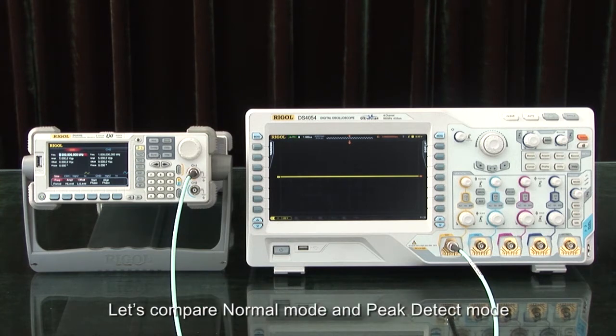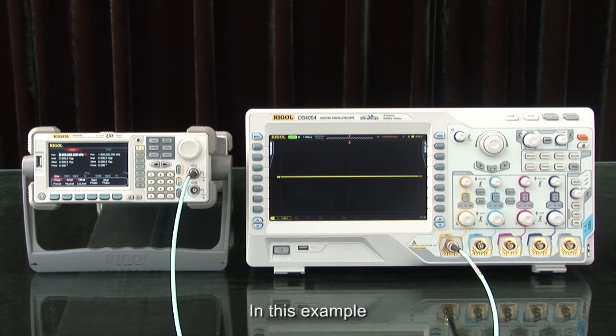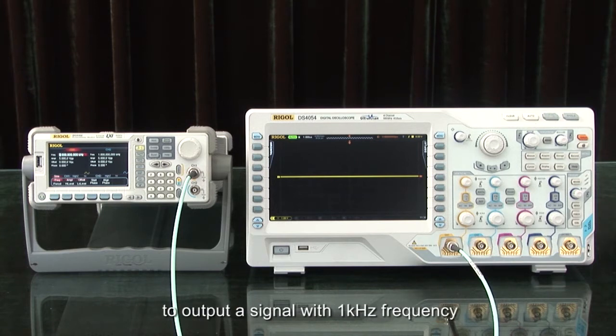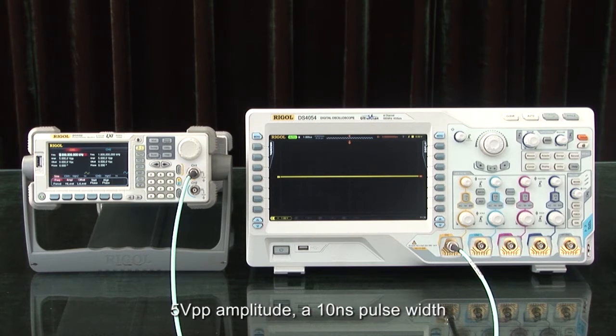Let's compare normal mode and peak detect mode. In this example, we are using a Rigol DG5000 arbitrary waveform generator to output a signal with 1 kHz frequency, 5 volt peak-to-peak amplitude, and a 10 nanosecond pulse width.